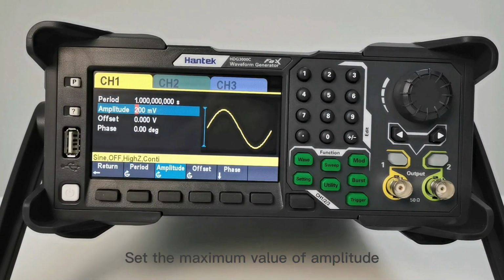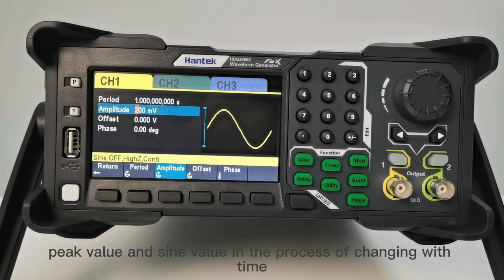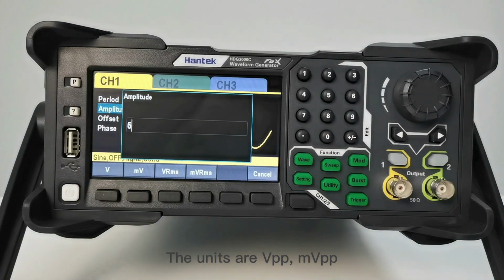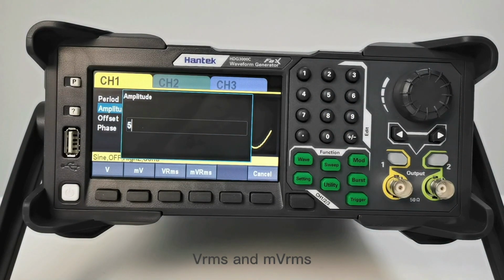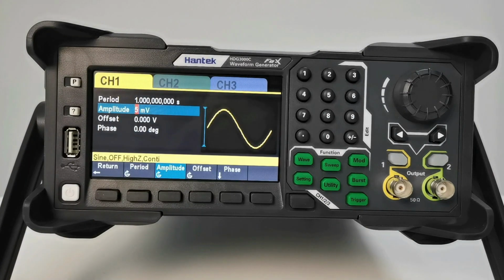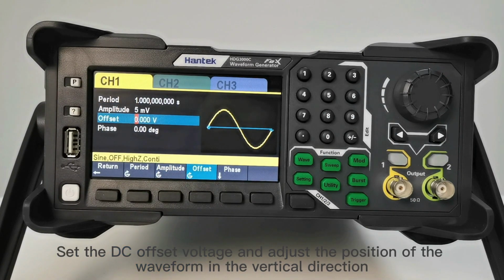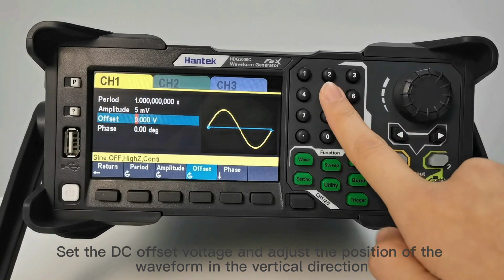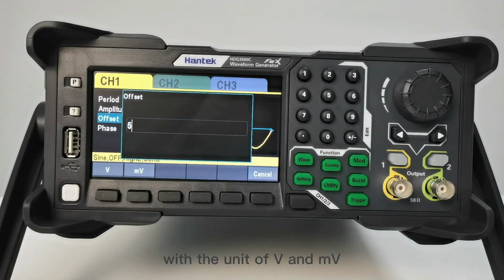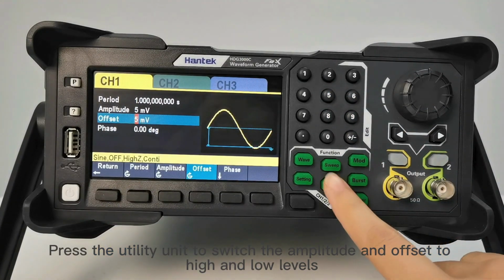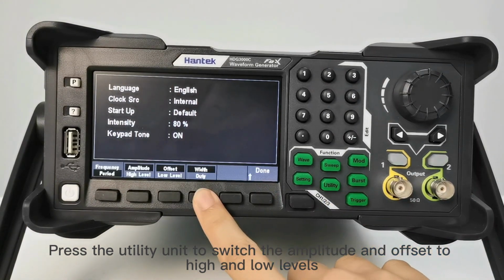Set the amplitude, that is, the maximum value, the peak value of the sine wave as it changes with time. The units are VPP, MVPP, VRMS and MVRMS. VPP equals 2√2 VRMS. Set the DC offset voltage to adjust the position of the waveform in the vertical direction, with the unit of V and MV. Press the Utility unit key to switch the amplitude and offset to high and low levels.